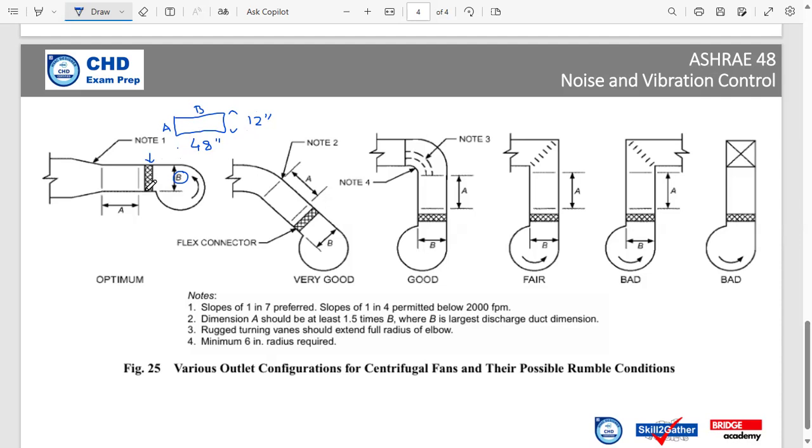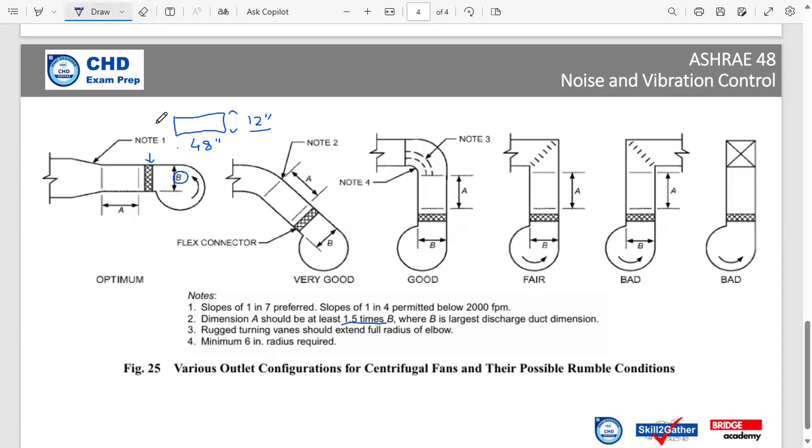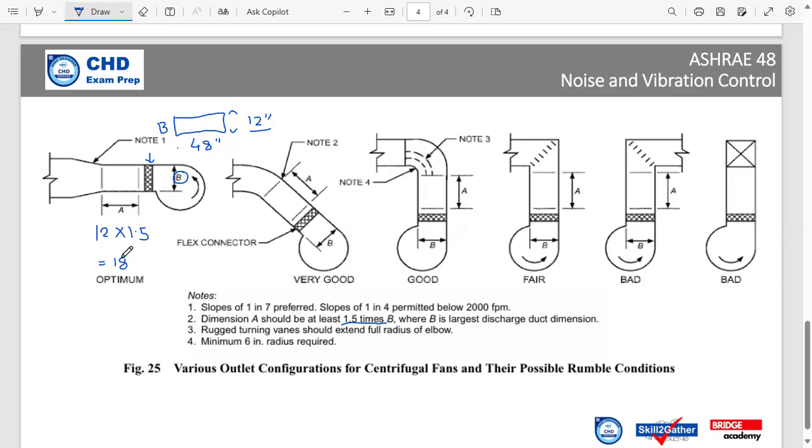So if the opening is 48 inches by 12 inches, we have to carry on the duct similar to the size of the opening for a length at least 1.5 times of B. So if here we see the B is 12 inches, 1.5 times of B, that means 12 multiplied with 1.5, what we have is 18 inches. This is the minimum length we should carry on a straight duct similar to the size of the centrifugal fan opening.